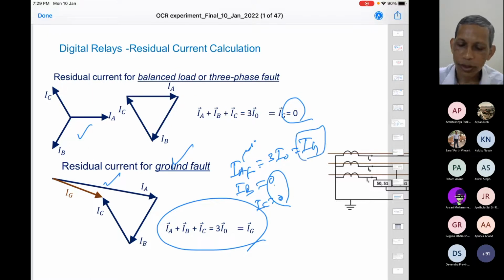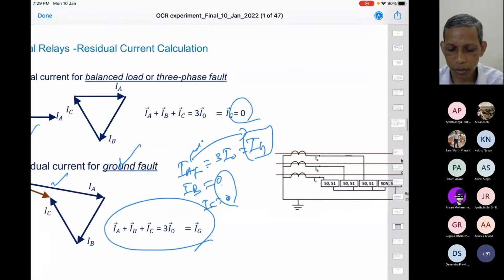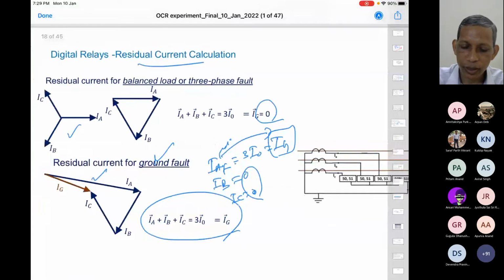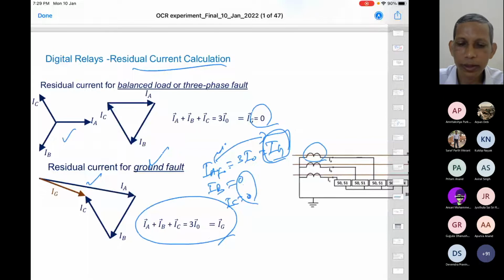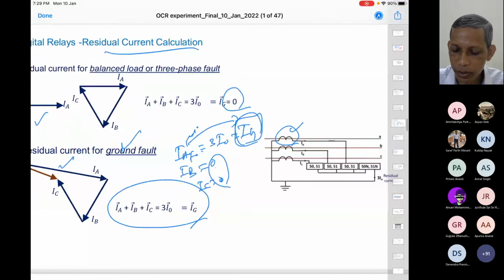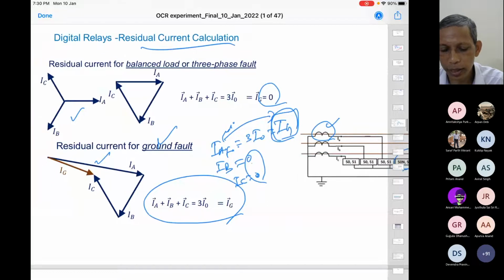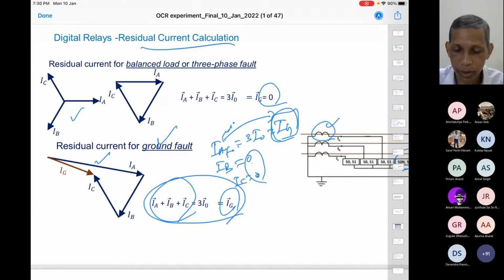The ground current will now be the same as the phase current in phase A. Whichever phase is involved with the fault, that current will flow to the ground in this kind of situation. That is what we call the residual current, or the ground current, and it can be obtained from this current. The information is the same. So if the 51 or 50 function is being used, it can also find the corresponding ground current by doing IA plus IB plus IC, and that is nothing but the ground current. They need not measure the ground path current separately.